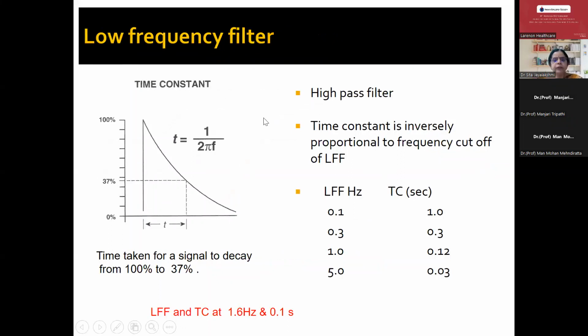So here it's important to know what is the relation between time constant and low frequency filter in the EEG machine. Both are inversely proportional. So the time constant is inversely proportional to the frequency cutoff of the low frequency filter. Normally, we keep the low frequency filter around 1, with a time constant of 0.1. What is time constant? It is the time taken for a signal to decay from 100% to 1/3.